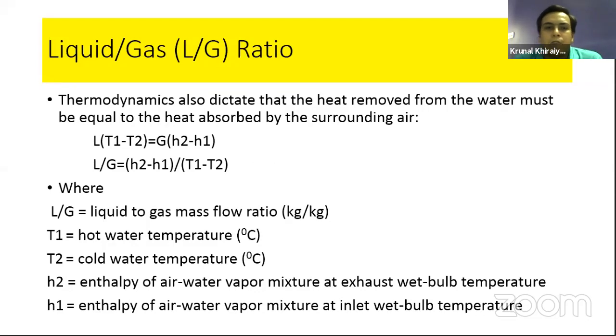How can we calculate the L2G ratio? Here I'm using a very simple thermodynamic equation, the energy balance equation. So m Cp delta T, and here I'm using the notation L, T1 minus T2 equals G into H2 minus H1. So if I make L by G, that equals H2 minus H1 divided by T1 minus T2. Here the most important terms are the unit balancing, because generally we measure enthalpy in kilojoule per kg from the psychrometric charts. H1 and H2 mean the enthalpy of the air before it enters the cooling tower and as it leaves the cooling tower. So we need to measure the enthalpy of the air-water vapor mixture at the inlet and outlet. Using the temperature measurements and the psychrometric chart, we can calculate this enthalpy, and the temperature we are measuring.